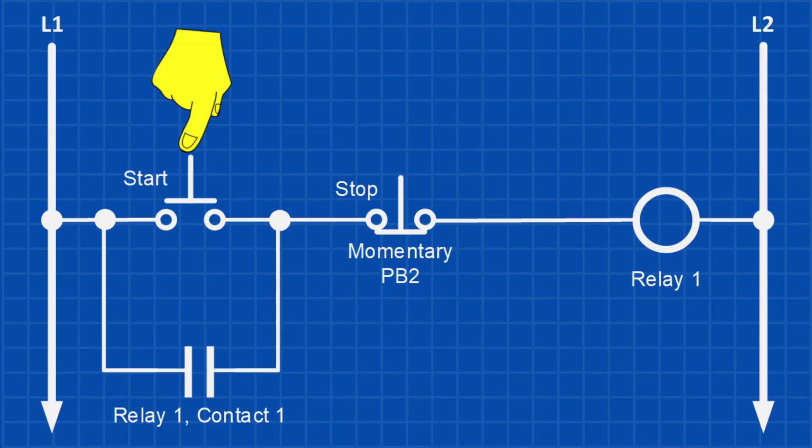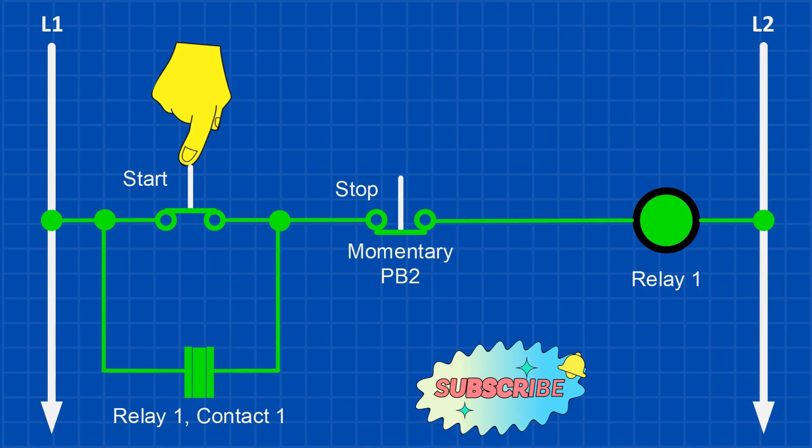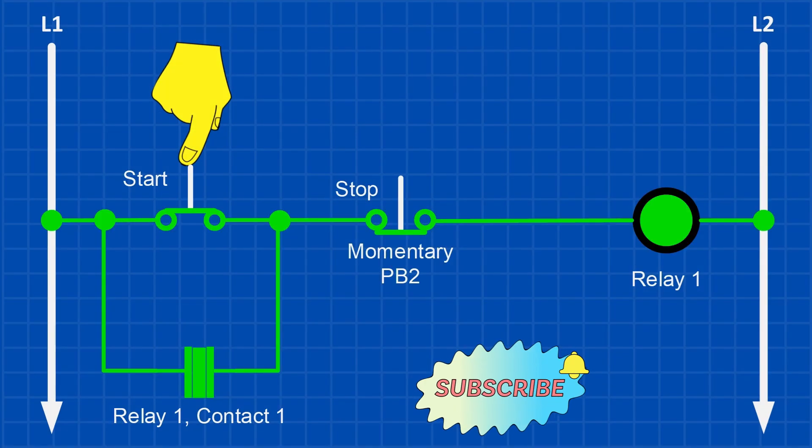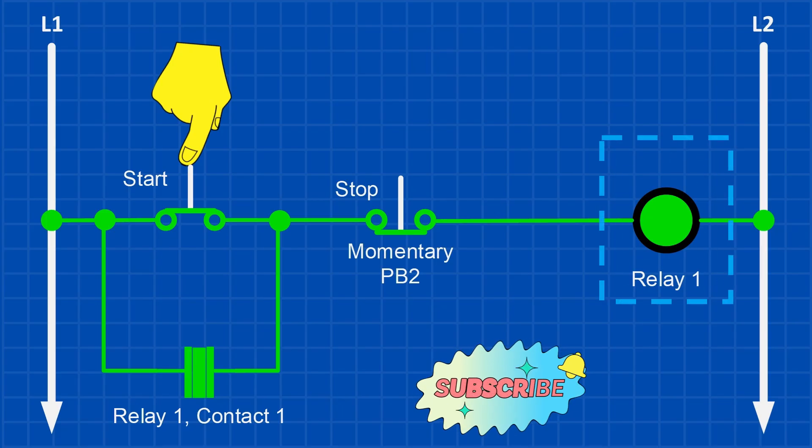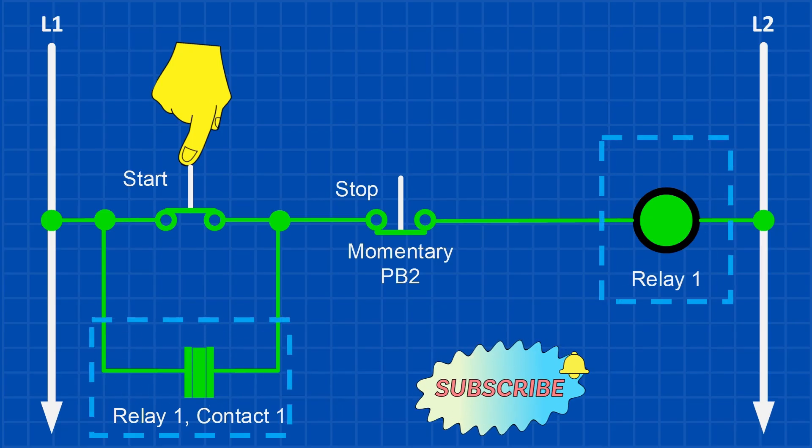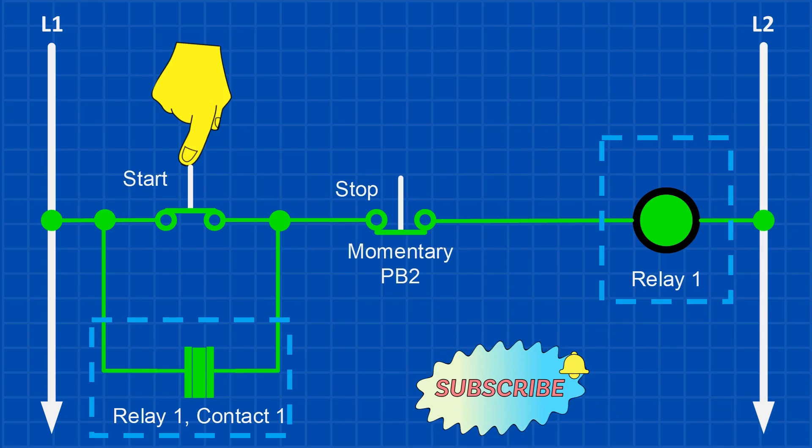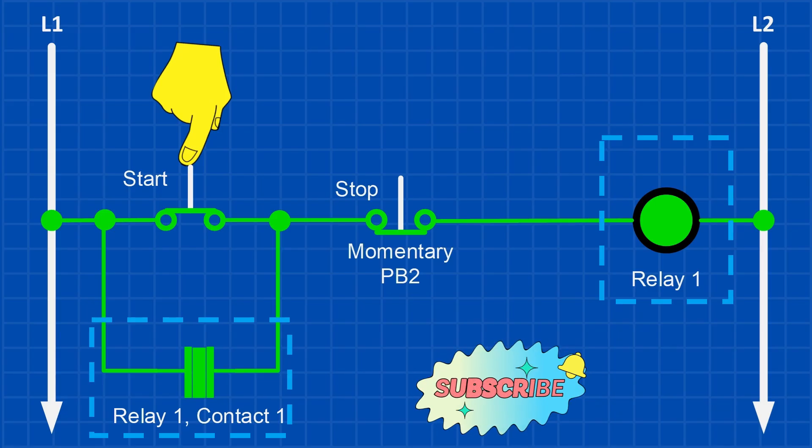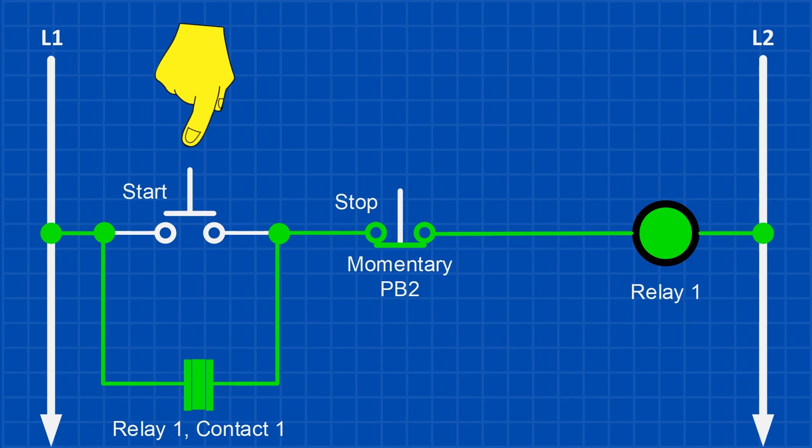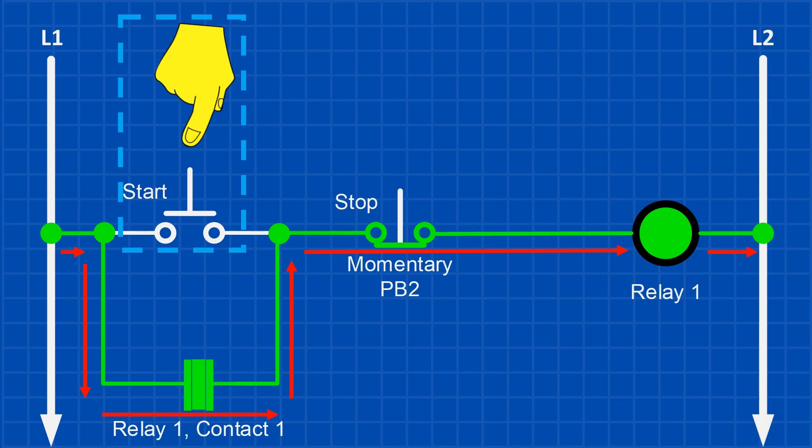So how does a latching circuit work? This is the simplest form of latching circuit in relay logic. When the momentary normally open push button is pressed, relay one energizes. This closes contact one, a normally open contact from relay one, which is wired in parallel with the push button. Because contact one is already closed and passing current, releasing the push button doesn't break the circuit. Relay one stays on.